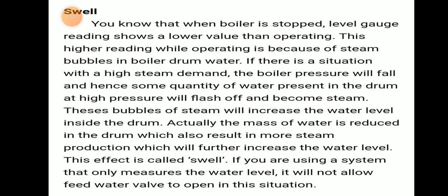Actually, the mass of water is reduced in the drum, which results in more steam production, which further increases the water level. This effect is called swell.